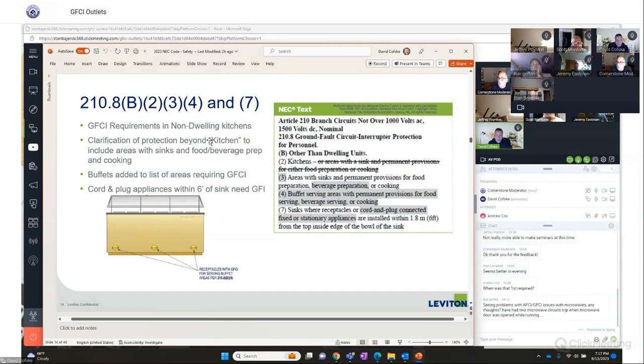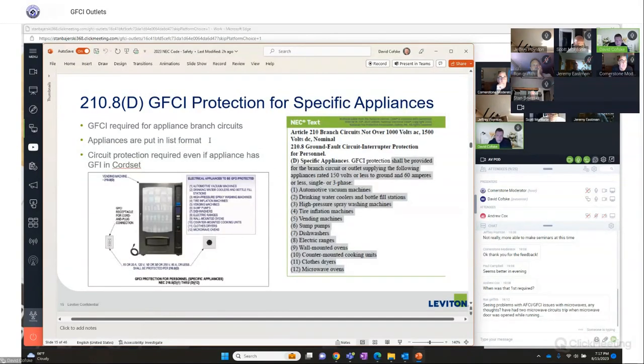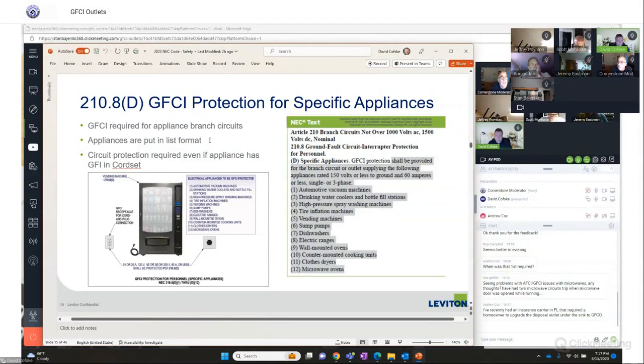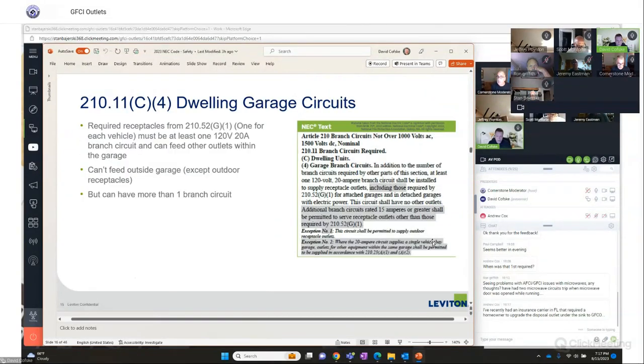This other 210.8 section basically is adding, if there's some type of an island, or they refer here to a buffet as well, those areas need to have GFCI protection under the current code. This goes into the same 210.8 section D, and some of it is in areas that are not residential, but from like 6 down, it gets into some of the residential stuff, such as sump pumps, dishwashers, electric ranges, wall-mounted ovens, counter-mounted burners, clothes dryers, and microwaves. All that stuff now is required to be on GFCI.